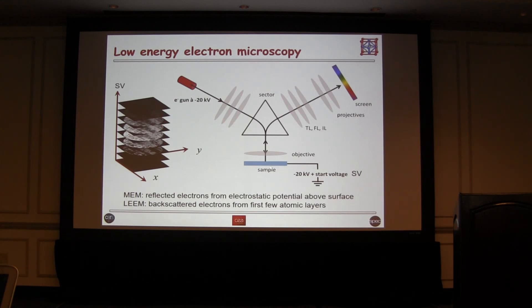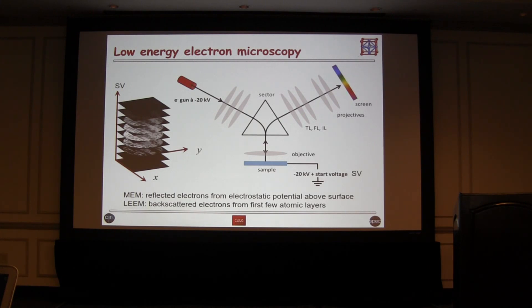Therefore, the electrons arrive at the sample surface and interact with the surface potential at an extremely low energy of the order of an electron volt, and therefore they are very sensitive to any modulation in the surface potential. The electrons are reflected or backscattered, then they go through the sector field, deviated in the opposite direction, through a projection lens, and we get the image on the screen.